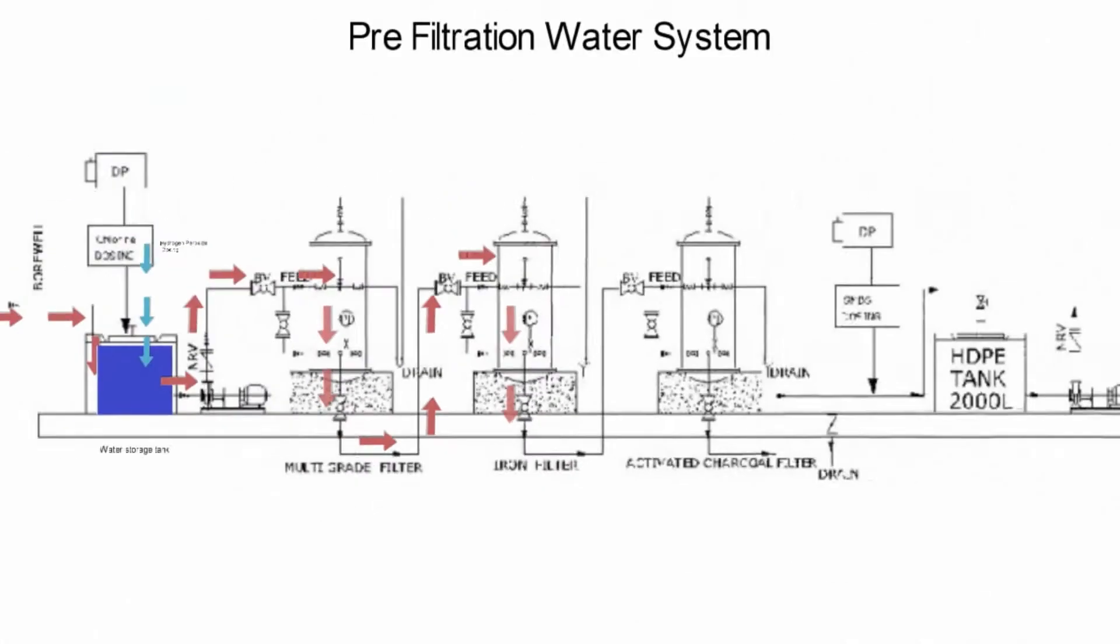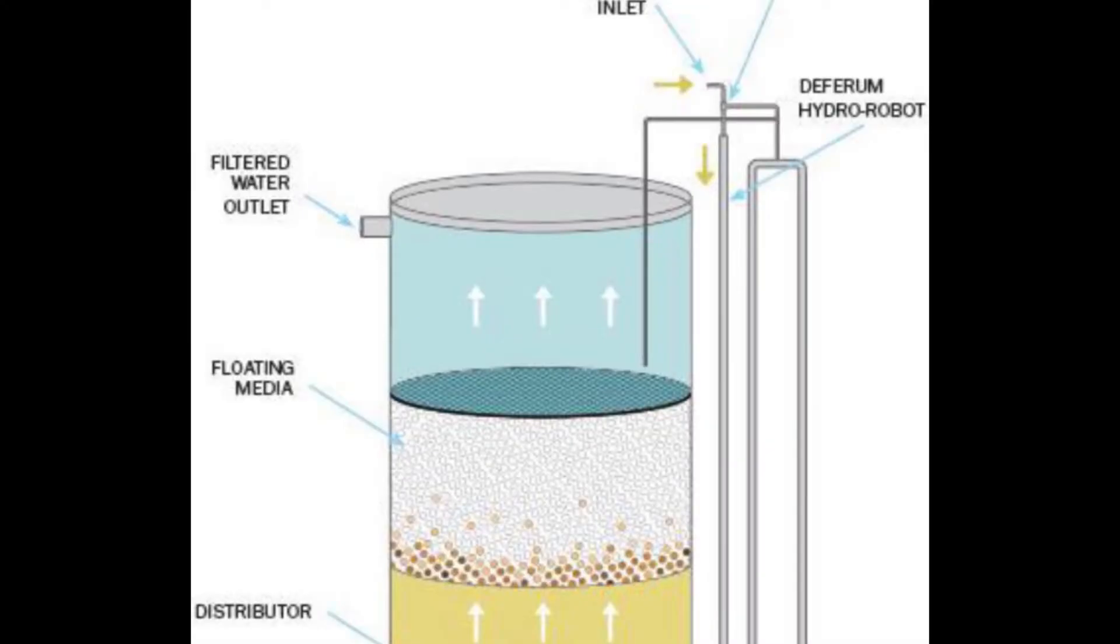Water from the multi-grade filter is then passed through iron removing filters. The process through which iron is removed from water is known as oxidation filtration, which involves oxidation of soluble forms of iron and manganese to insoluble forms, which are then removed by filtration.